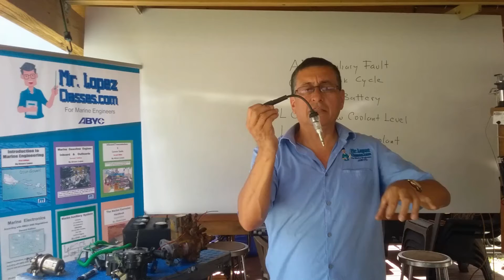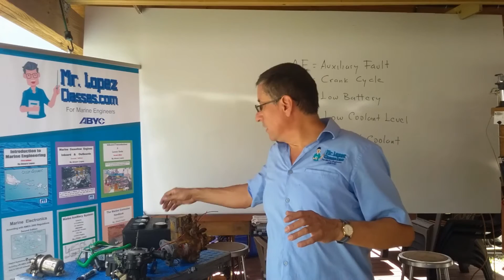Suppose that the generator is gasoline. I need to know if it has spark. I use this proof, to verify, I introduce this one on the spark plug and the cable here. And I crank and I verify in each cylinder if I have a spark. If I don't have a spark, I need to follow the procedure that I explained in our marine gasoline book. The procedure on the coil, the procedure on the distributor. You need to follow all of those steps in order to verify why I don't have a spark on the spark plug. For that reason, the engine doesn't start.